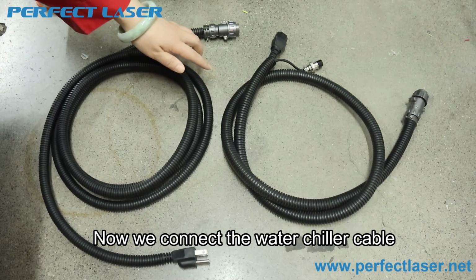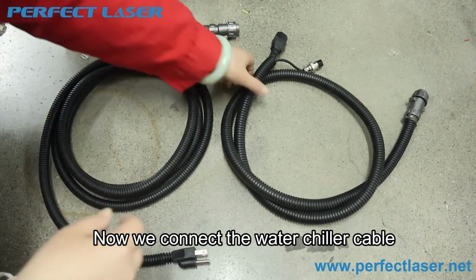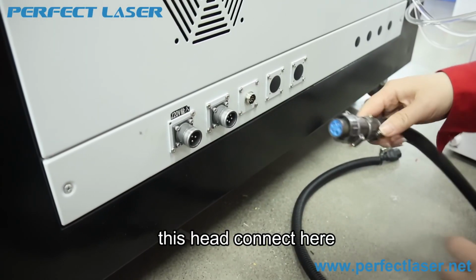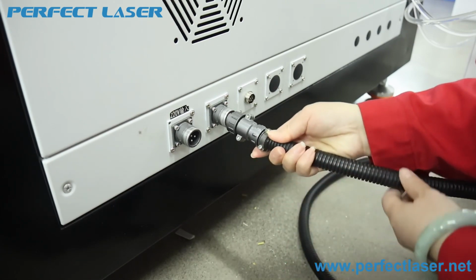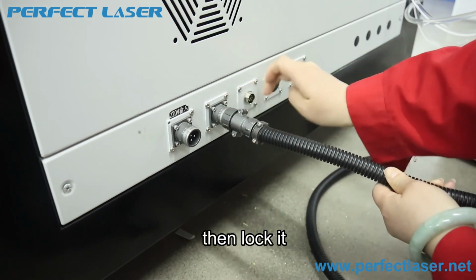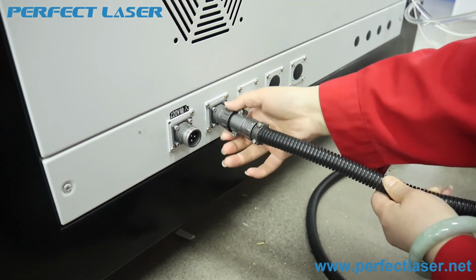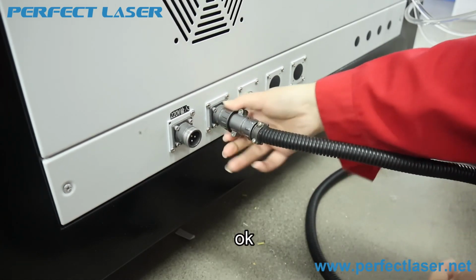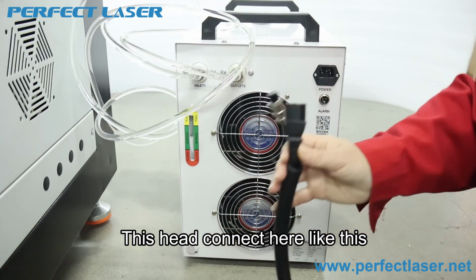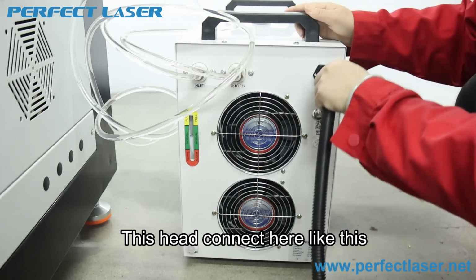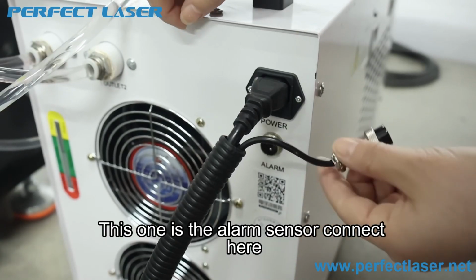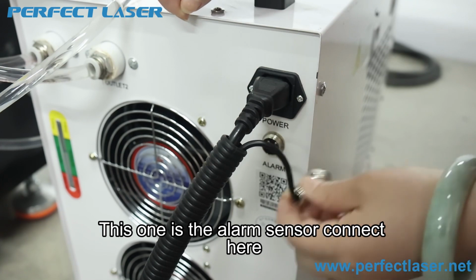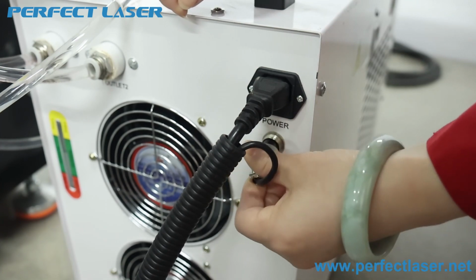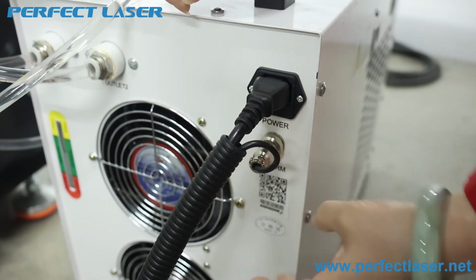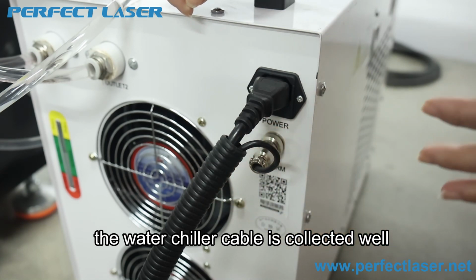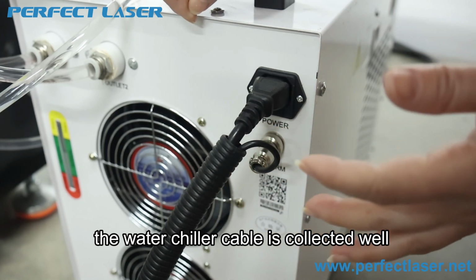Now we connect the water chiller cable. This head connects here. Then lock it. Okay, this head connects here, like this. This one is the alarm sensor cable coming here. Okay, the water chiller cable is connected well.